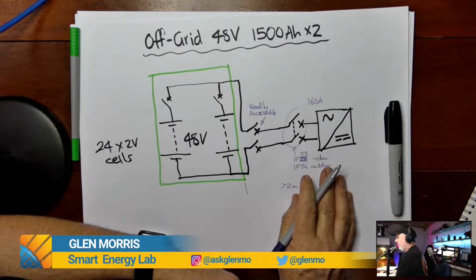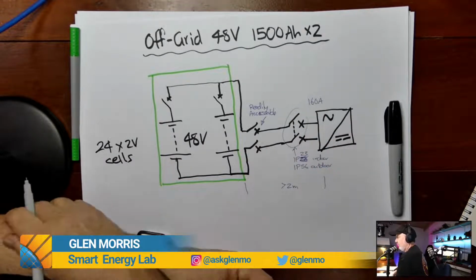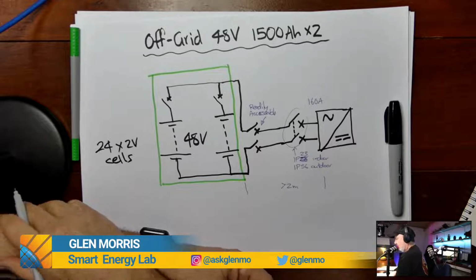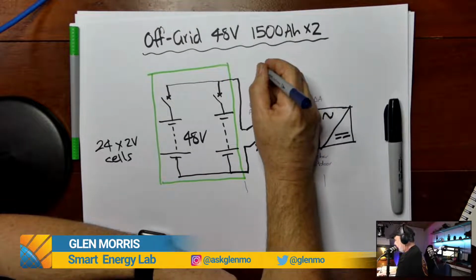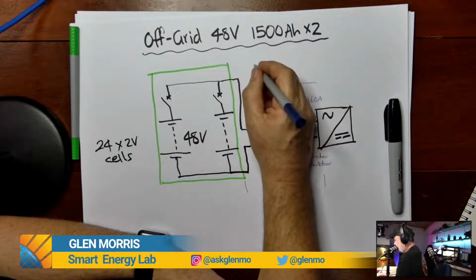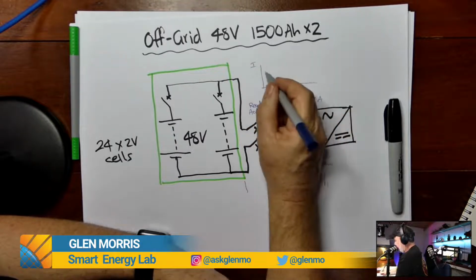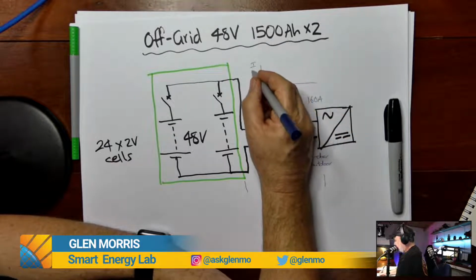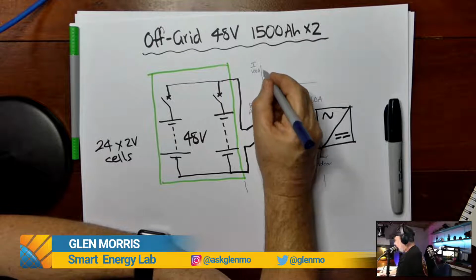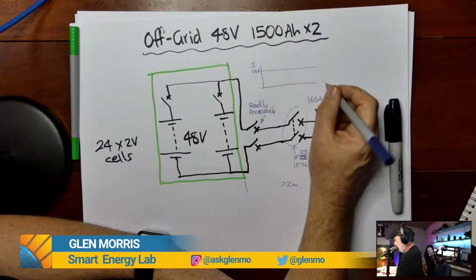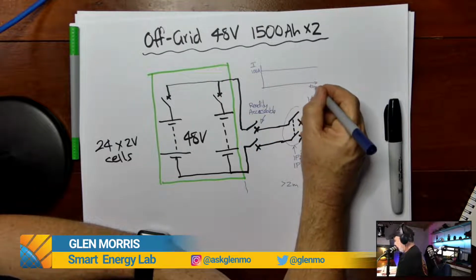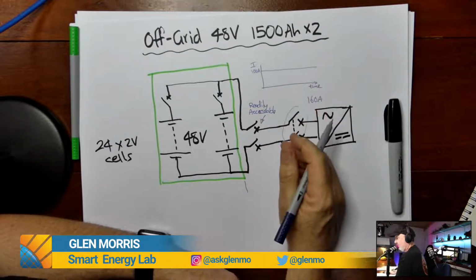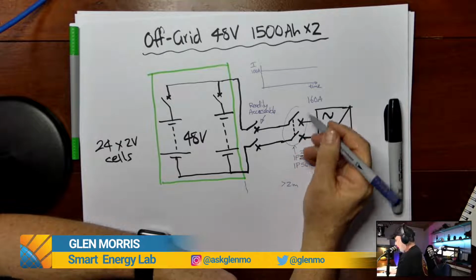And the other consideration, which is a tricky one, is known as ripple current. Now when you've got, if I do a little graph here, so this is current here, you might think a DC current looks like this. So say we've got 100 amps of current, and you might think it looks like that over time. So this is time across the bottom here. So you might think, oh well, it's 100 amps, as long as our device can carry 100 amps without tripping.